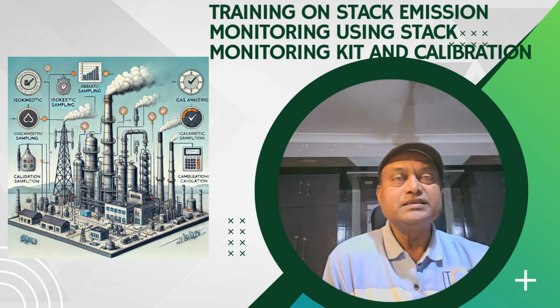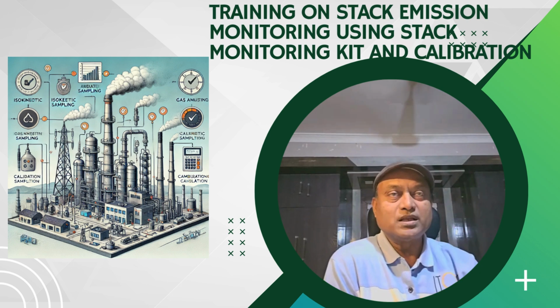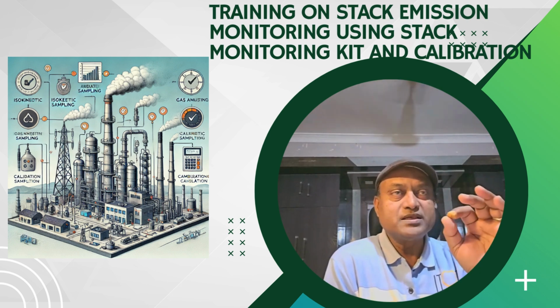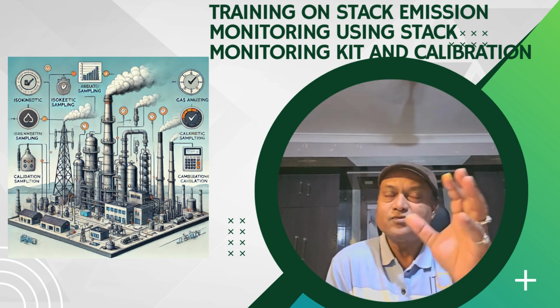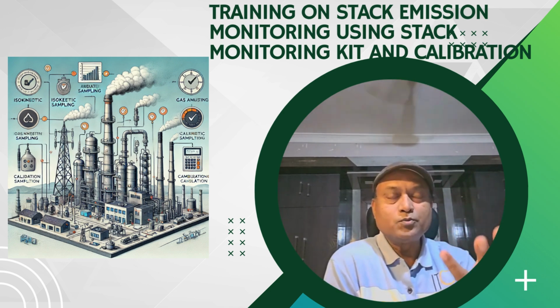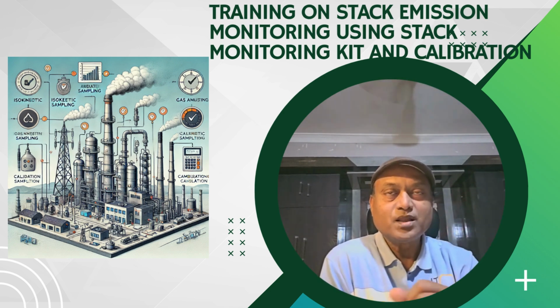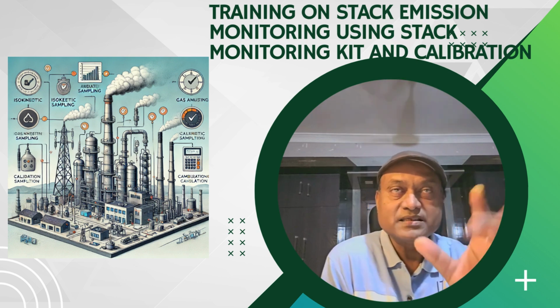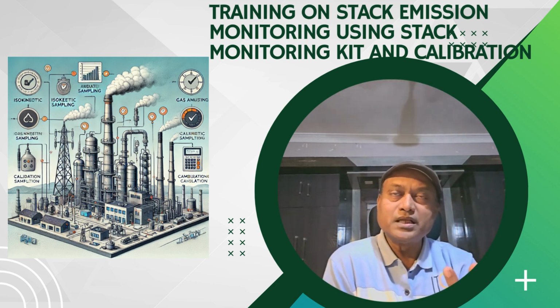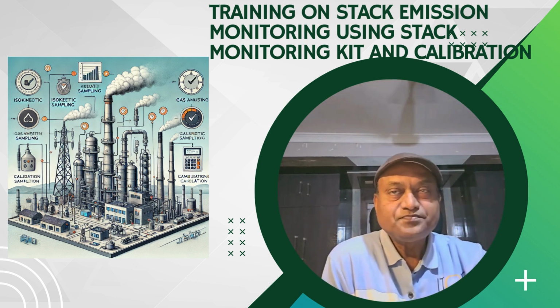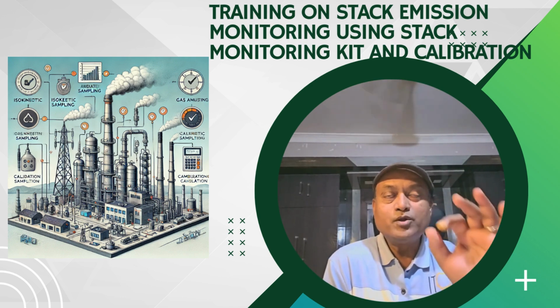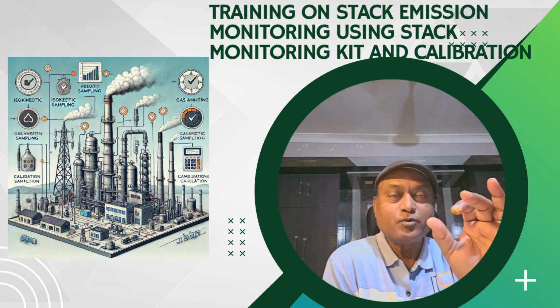Non-isokinetic condition is generally used for gases only. Simpler methods can be used without matching flow rate. That is, when you are going to measure only gases, not the particulate matter, then you can use the non-isokinetic sampling method.